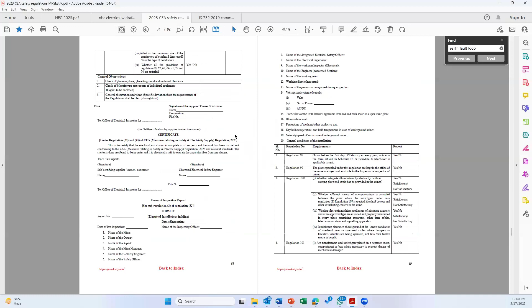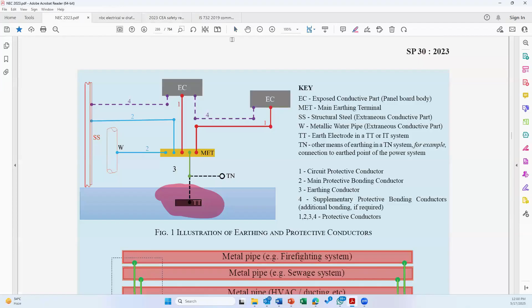For example, here, this is the annexure from the CEA regulation. Is protective equipotential bonding tested is one requirement. Is fault loop impedance at the origin of installation measured? Is fault loop impedance at each circuit tested? Is fault loop impedance tested for all sources? So basically, this updation happened in, sorry, not NEC, the regulation happened in 2023. Of course, the information about fault loop impedance is not new. It was existing in the standard since 1966, when fault loop impedance first came into existence in the standard.